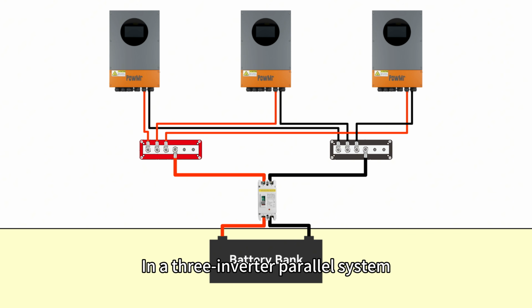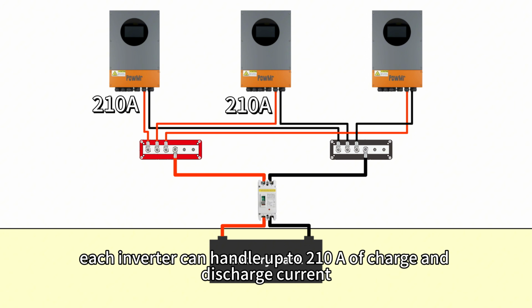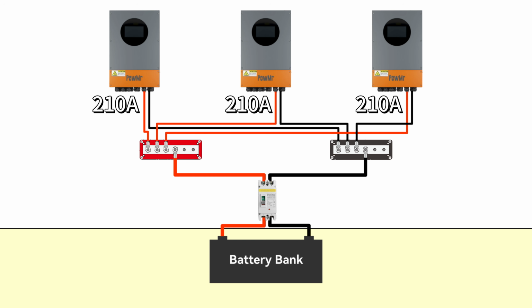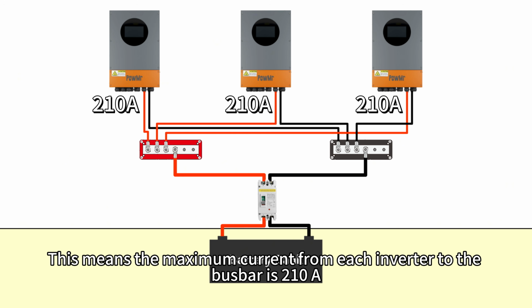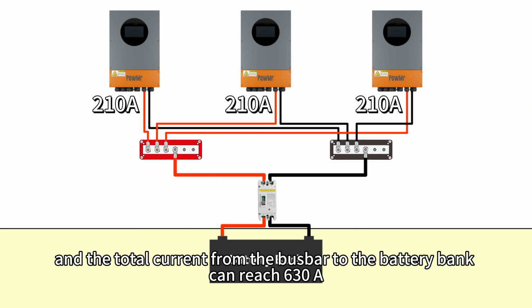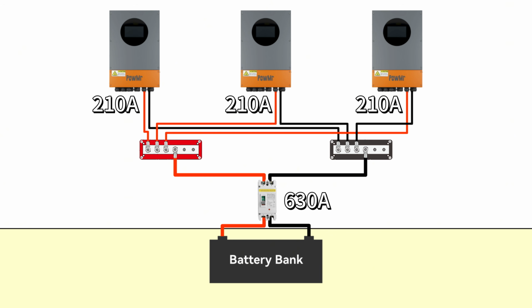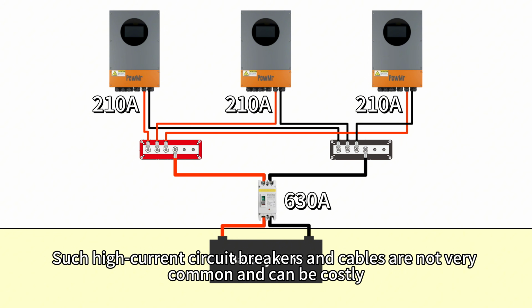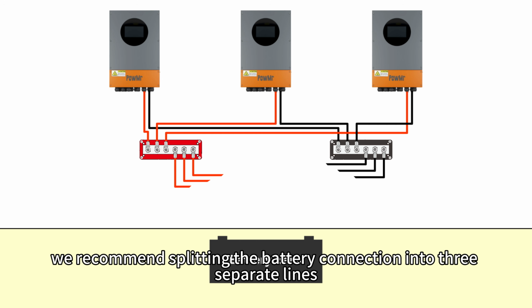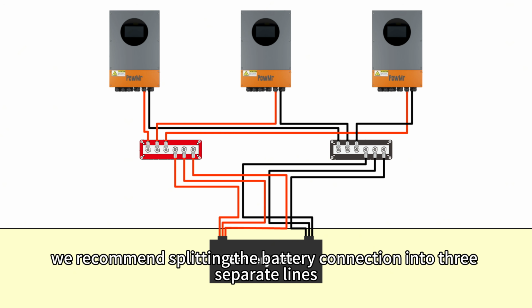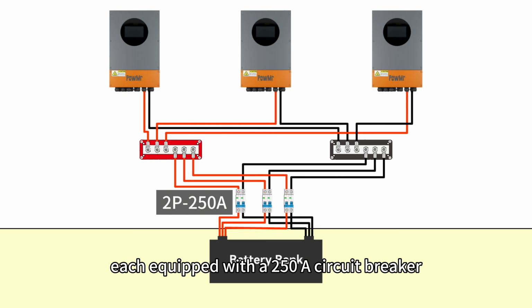In a 3-inverter parallel system, each inverter can handle up to 210 ampere of charge and discharge current. This means the maximum current from each inverter to the bus bar is 210 ampere, and the total current from the bus bar to the battery bank can reach 630 ampere. Such high current circuit breakers and cables are not very common and can be costly. Therefore, we recommend splitting the battery connection into 3 separate lines, each equipped with a 250 ampere circuit breaker.